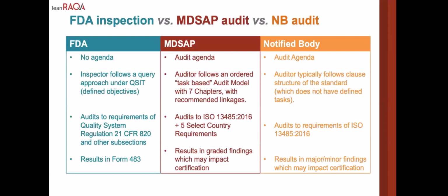FDA will show up with no agenda because they are there to carry out the QSIT, and they are going to follow the queries outlined in the QSIT. Audits of the requirements to 21 CFR 820, and they are going to issue you a Form 483.